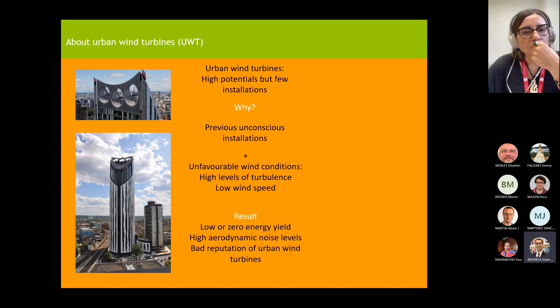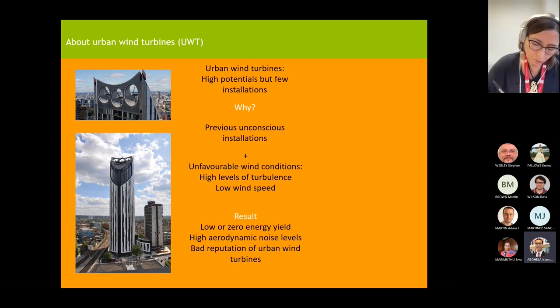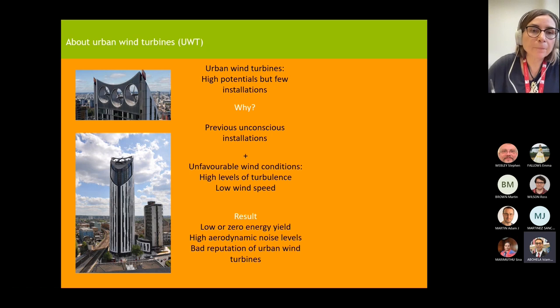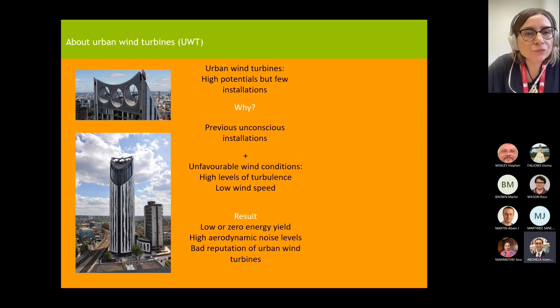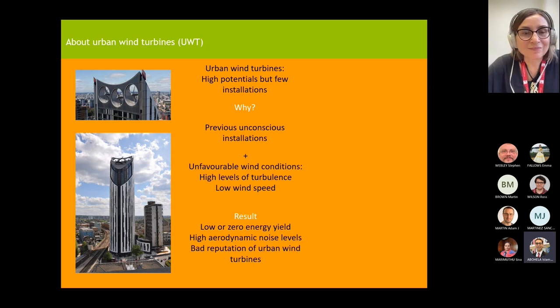The building in Elephant and Castle, London, had three roof-mounted wind turbines installed, expected to generate 8% of the building's power — and they were doing so. However, due to vibration and noise from the wind turbines, they were shut down because there were too many complaints, apparently from a restaurant on top of the building. We need to investigate the conditions needed for these wind turbines to be efficient and operating properly.